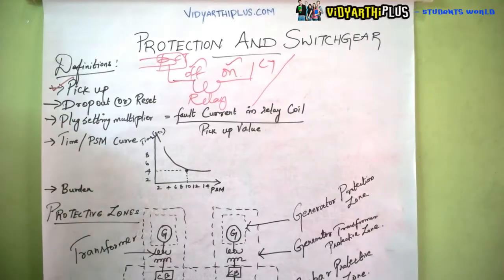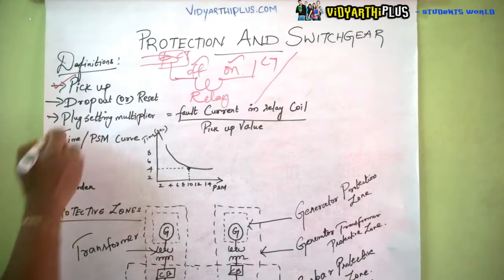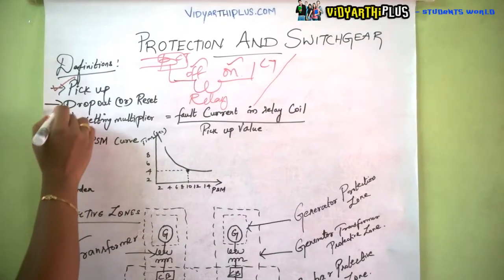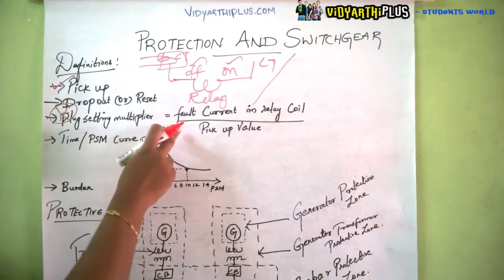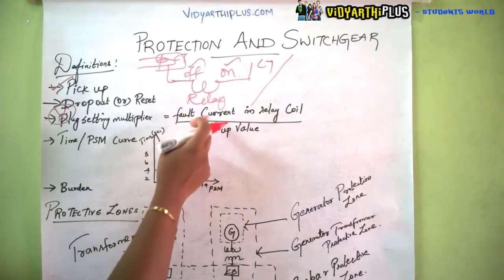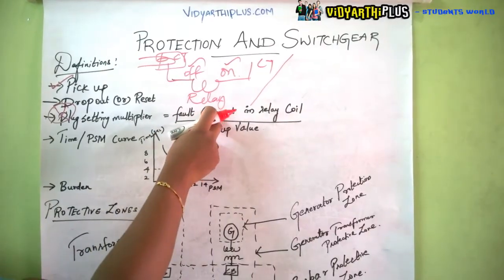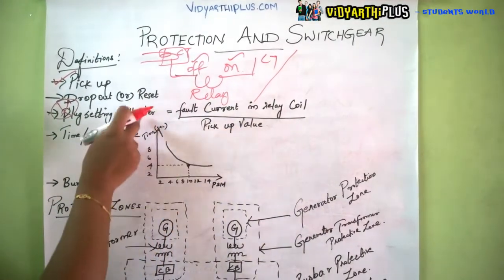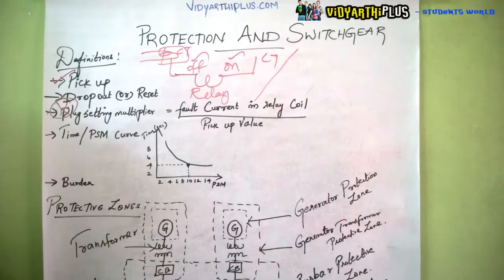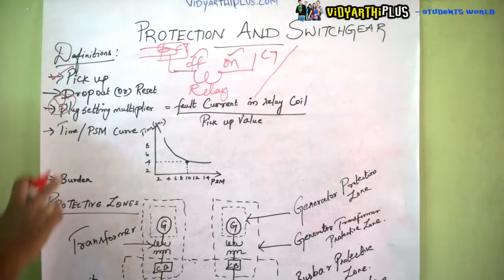Next is the plug setting multiplier (PSM), which is a very important term. The plug setting multiplier is given by the ratio of the fault current in the relay coil to the pick up value.